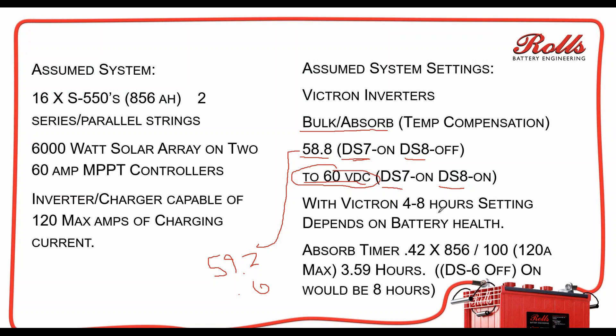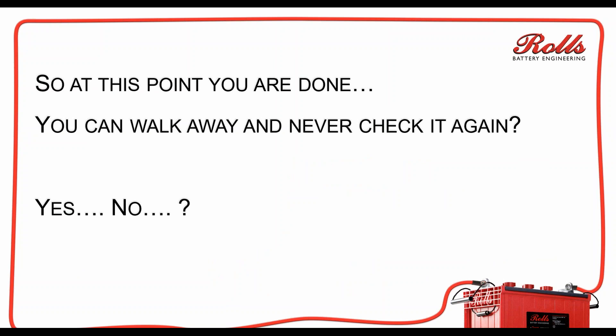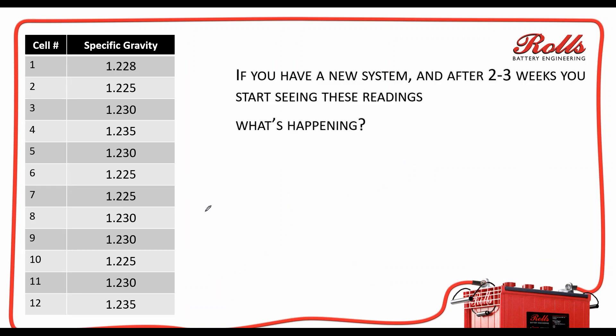With Victron, the absorption time settings are four to eight hours. Unfortunately there's not a whole lot of resolution on that — it's either four hours or eight hours. Normally, with this system you're looking at a 100-amp charge source on an 856 amp-hour battery bank, so it should be set for right around four hours. If the DS6 dip switch setting is on, the setting is going to be eight hours, and you could have some excessive gassing situations with that.